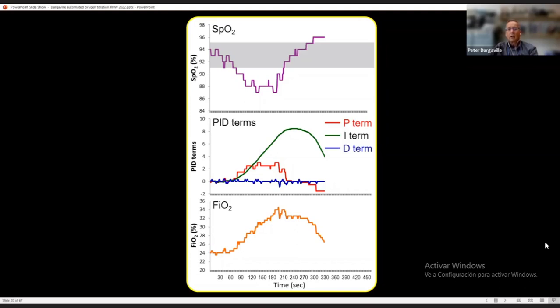As you can see here, we've just overshot slightly, and we can quickly get back down into the target range of SpO2 as the integral term reduces back to zero, and the proportional term now is less than zero, and the FiO2 as a result of those goes back down to the baseline. So that in a nutshell is what we're expecting from the PID approach, and that applies to so many systems universally, as I've said. Now I'm going to turn to the clinical effects of automated oxygen control and discuss what we know in the NICU and also in the delivery room.